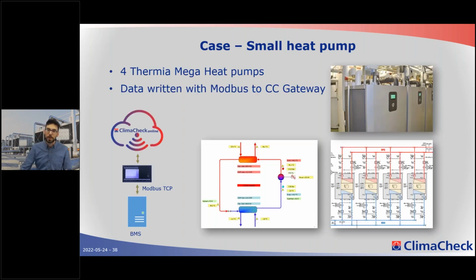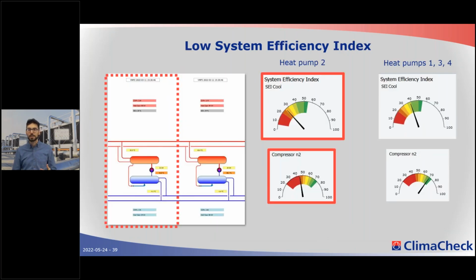This is an example with four heat pumps, taking data already in the BMS system via Modbus and using our tool for analysis. Here we can see heat pump number 2 has a very low system efficiency index compared to the other three. In this case it's easy to compare them—we know how the others are working, and we can see this one isn't working properly.